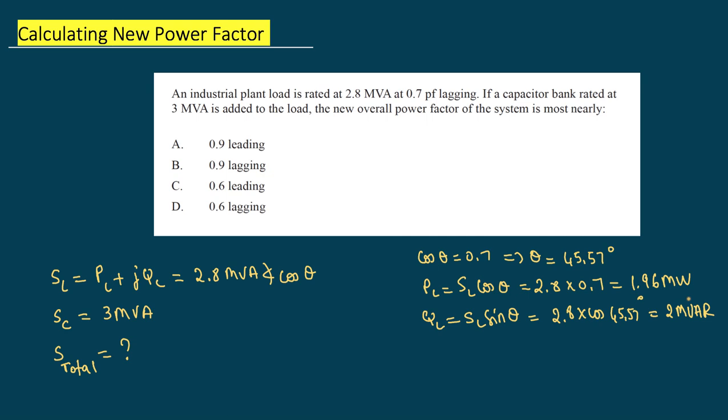Okay, so we have that for the load. So what about the capacitor, the cap bank? So we know that capacitors, they contribute, they generate reactive power, and so we are going to add the reactive power that the cap is contributing to the load, which will give us the entire system MVA, which we can then derive the power factor.